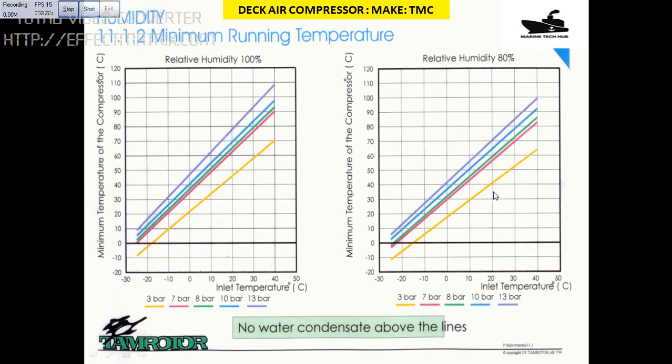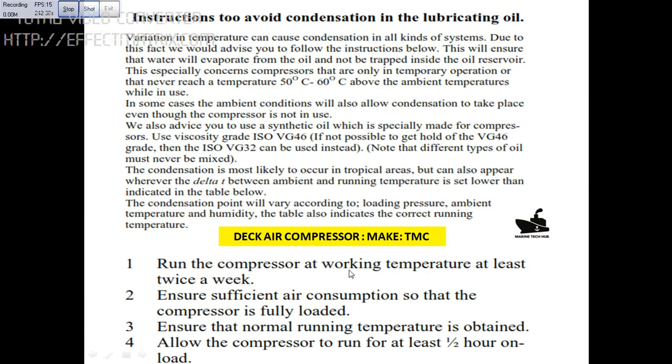If the temperature is below this line, there is a possibility that condensation is taking place, so you have to change the oil regularly if you are not maintaining the temperature. The important thing to note is: you need to run the compressor at least twice a week if you are not using the TMC compressor. Run it at full load for at least half an hour. When you run it like this, water condensation will not take place. If you are not running it, there is always the possibility that condensation will occur and you will spend a lot of money on maintenance of the Deck compressor. Please remember this for safe running, and to save money and time for the company. Thank you.